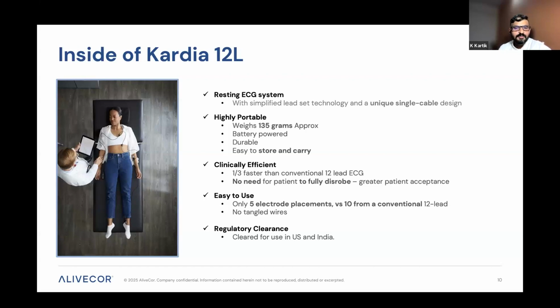Clinical efficiency wise, it is known to be faster than the conventional 12 lead ECG in terms of acquisition time. And there is no need for the patient to fully disrobe, which means greater patient acceptance. Easy to use, yes. Instead of the conventional 10 electrodes, only 5 electrodes are used in terms of placement, right? And since it's a single wire, there is no concern of wires getting tangled while it is placed on the patient's body, which saves a lot of time in the overall setup of the ECG test. And regulatory wise, it's cleared for use in the US and in India. It has FDA clearance, and it is CDSCO approved as well.